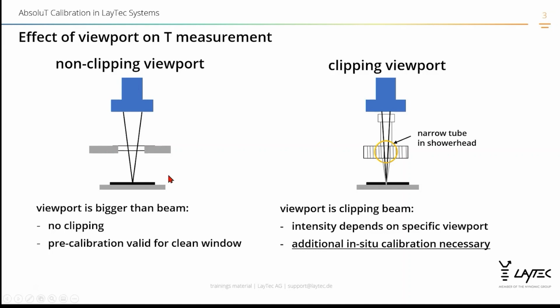But there are influences which will change this initial calibration. And here, we are talking about how to recalibrate it on site once after the installation is done, and from there on, at periodic times, to double check the temperature, a very important parameter which you really need to be accurate in order to fully understand and use its capabilities. Repeat this and recalibrate it on site.